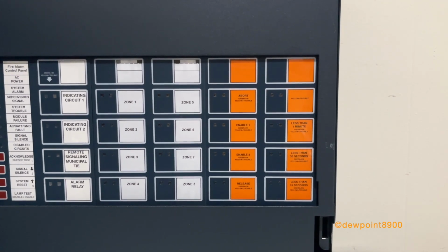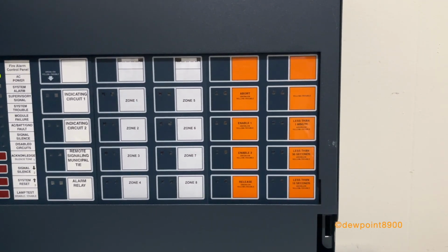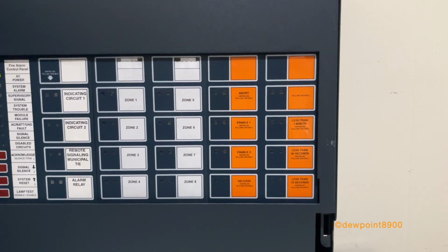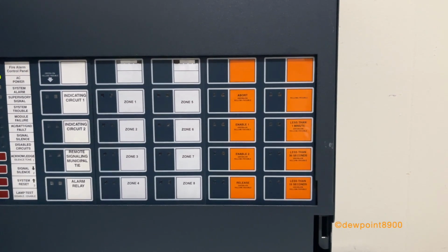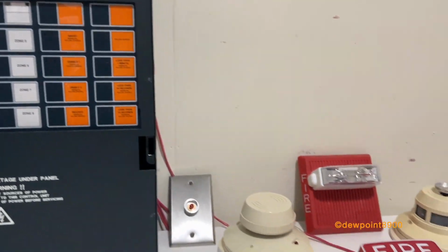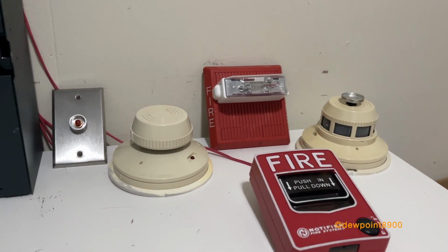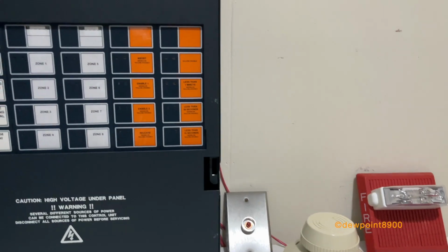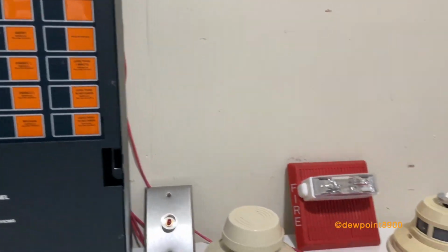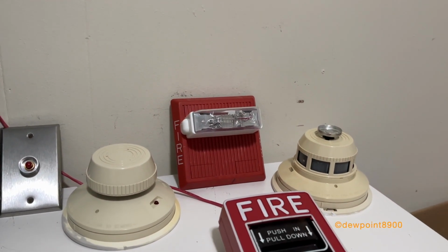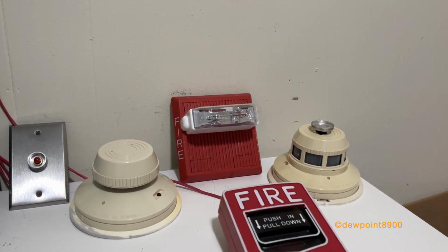While suppression systems can vary depending on the setting, most follow the same premise of cross-zoning, where 2 or more zones must be in alarm for the agent to get released. For this system, both of the detectors are on separate zones. If one of the detectors activates, the system enters first alarm stage, where the warning signal will sound in slow march time, and this goes on forever.